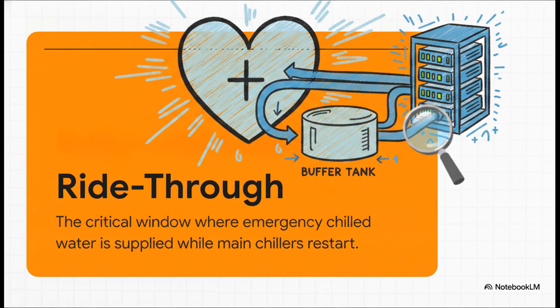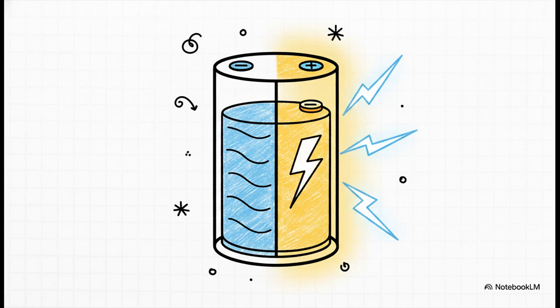And that terrifying gap is exactly why a concept called ride-through is absolutely vital. Ride-through is this critical operational window where emergency chilled water literally must be supplied while the main chillers are offline and booting back up. Think of it like CPR for the data center, right? When the heart of the cooling system, the chiller, temporarily stops beating, you still desperately need oxygen, or in this case cold water, to keep the brain alive. The buffer tank acts as that mechanical life support system. It provides this ride-through, keeping the servers breathing until those chillers finally come back online. Section 2. The giant thermal battery.